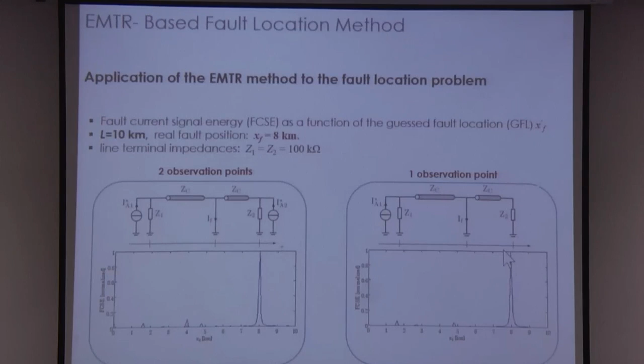We define a number of guessed locations in the network. We apply time reversal to the signal, and for each guessed fault location we simulate the network by back-injecting the time-reversed signal, and find the energy of the fault current. We know only at one point will the energy have a peak, and that is where our true fault location matches the guessed fault location.